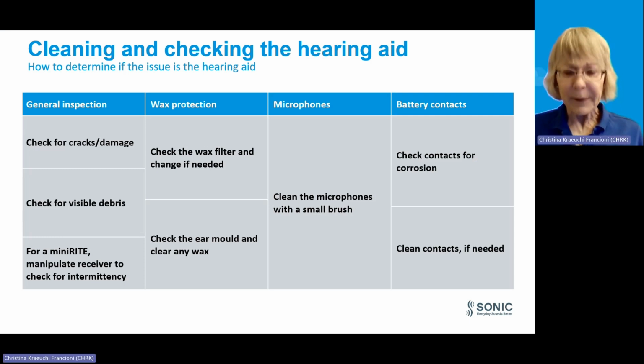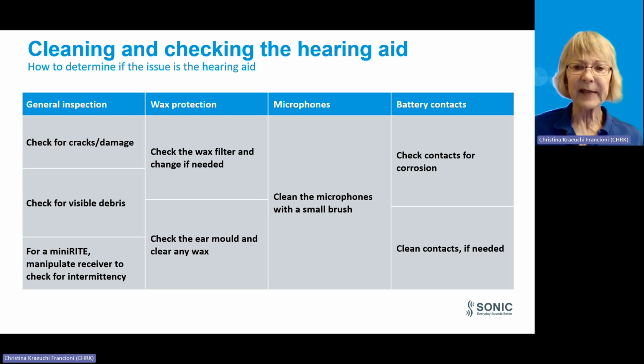Consider the next steps when cleaning and checking a hearing aid in your clinic. First, inspect the devices visually. Do the hearing aids look damaged in any way? Should the hearing aids need to go for repair, then the observations by a clinician are very, very useful for the service shop. Also check for visible debris and manipulate the receiver to check that it is not damaged.